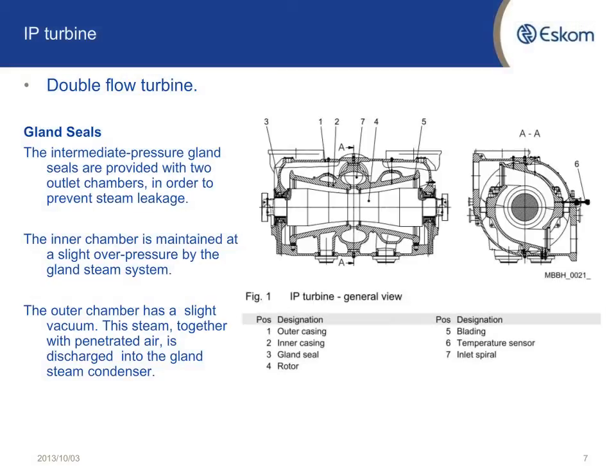For the IP turbine, the gland seals are almost the same except for the innermost chamber. The intermediate pressure gland seals are provided with two outlet chambers. The inner chamber is maintained at a slight overpressure by the gland steam system, and the outer chamber has a slight vacuum. Steam together with penetrated air is discharged into the gland steam condenser. I've also included an overview of the IP turbine showing the two steam bleeds in the middle of the turbine.